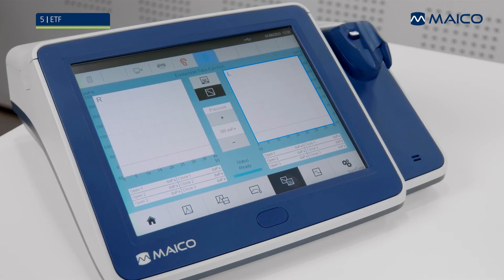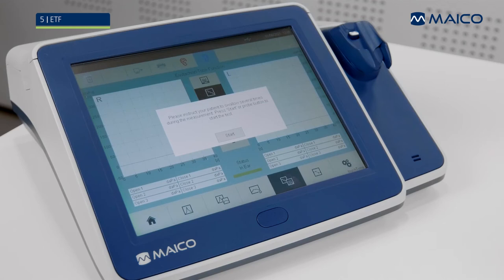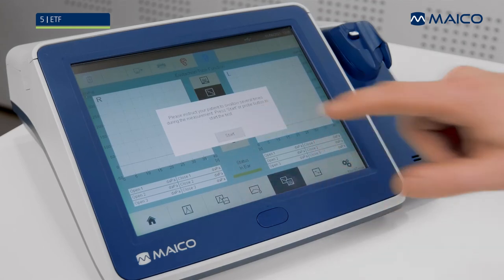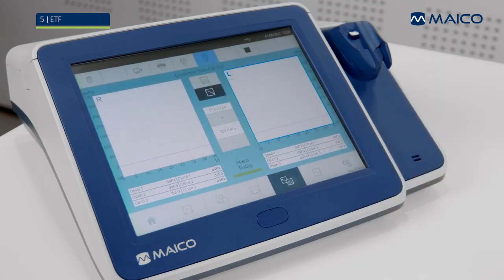Instruct the patient not to move or talk until the test is over. When a seal is obtained, the device displays a message to instruct the patient to swallow several times during the measurement. Press Start to begin the measurement. Pressure will increase to the selected start pressure. Let the pressure run a few seconds at peak pressure to verify a successful seal.